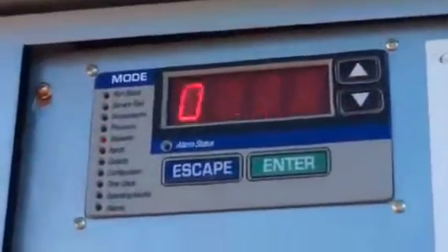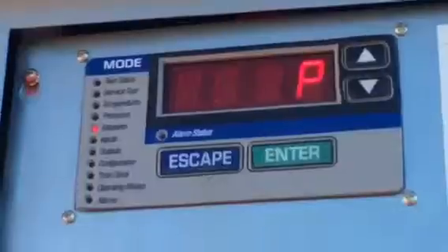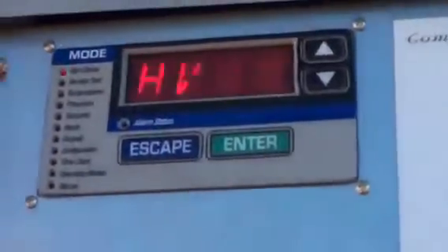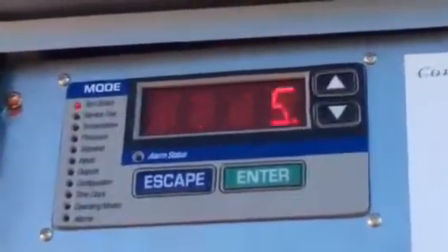What's cool, this thing tells you if the actuators are failed or jammed. It's all here. It's a great unit for a service tech. It tells us what's going on every step. If it's not a problem mechanically, you can call, say, hey, there's something wrong with your actuator, call an HVAC guy and have him take care of it. Yeah. Nice.